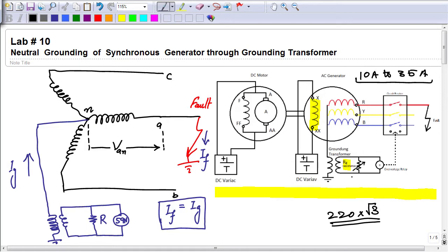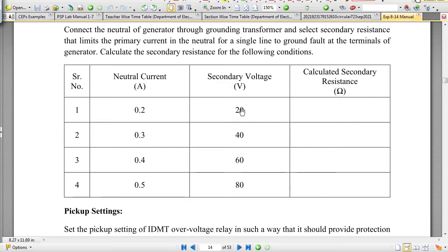Now let's see how we are going to design the value of this resistance, which will be inserted on the secondary side of this transformer. I have already mentioned that the voltage rating of the primary winding of this grounding transformer should be either equal to or greater than this line to neutral voltage of the generator. In our laboratory experiment, the rated voltage of the generator phase is 220 volt, and the same is the case here. We will use the primary winding rating equal to 220. The secondary side may have different values. Practically I have said that it could be 120, 240 or 480 volt, but in the laboratory experiment students will use these voltages for the secondary winding: 20 volt rating, 40 volt, 60 volt and 80 volt.